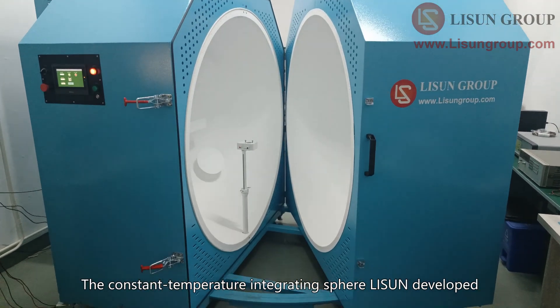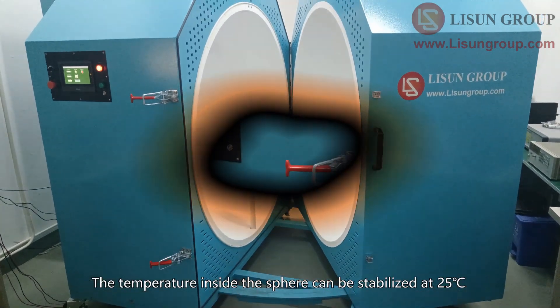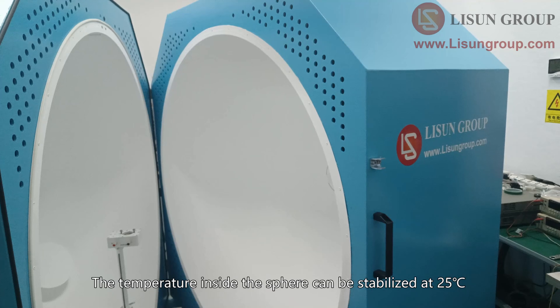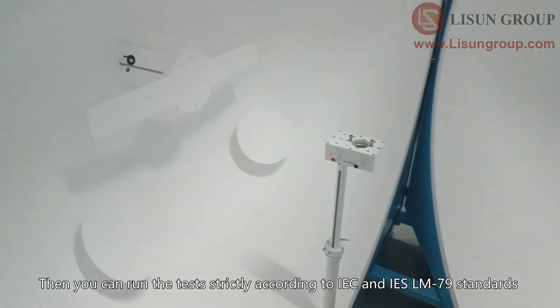The constant temperature integrating sphere Lisun developed has built-in refrigeration, heating and air circulation systems. The temperature inside the sphere can be stabilized at 25 degrees Celsius, so you can run tests strictly according to IEC and IES LM79 standards.